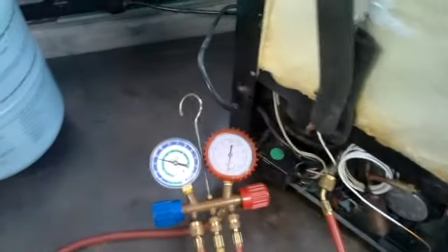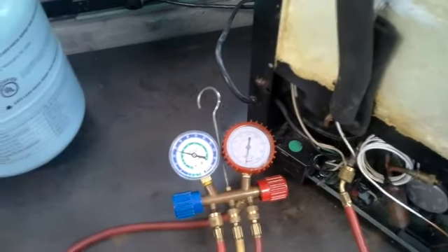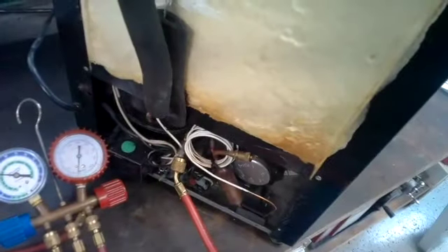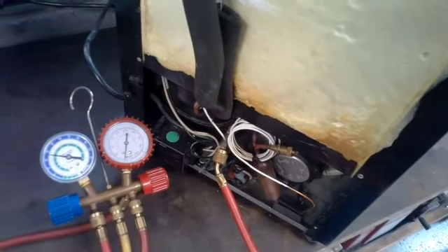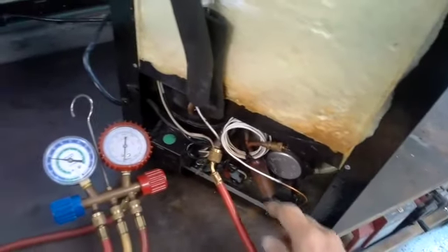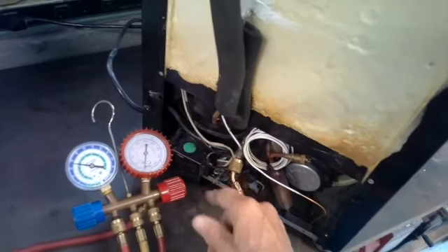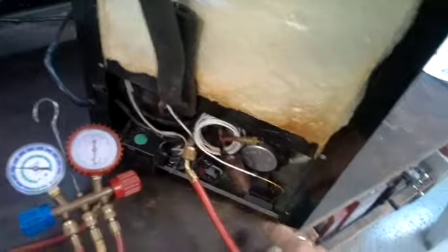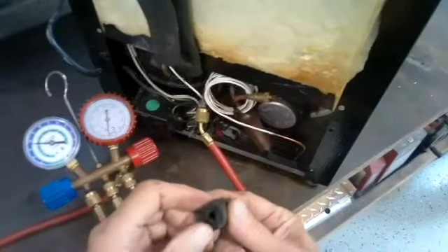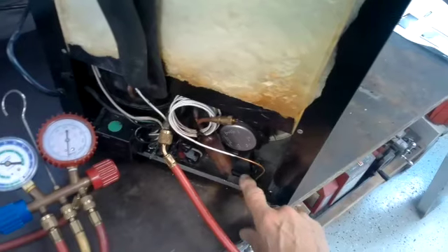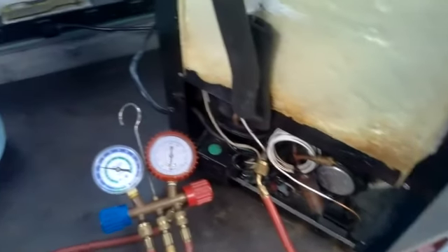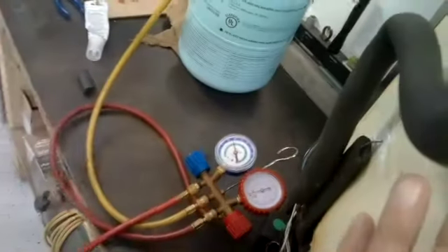Okay, here we are. Now we put some Freon in there last night and let it sit overnight, and it's still holding pressure. The pressure came down about 10 pounds because the temperature in the garage, the shop, has dropped. So I'm going to assume that there are no leaks. I cleaned everything up here and put some cable ties around the wires so there's no vibration. I put a little piece of rubber insulation underneath the filter dryer where the cap tube goes in, so there's no vibration there. So now the next thing to do is to finish recharging it.